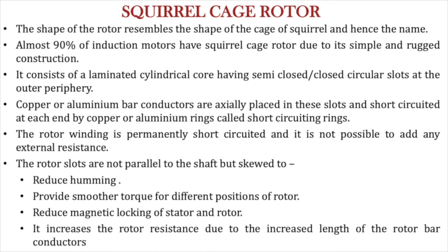The rotor slots are not parallel to the shaft but skewed to reduce the humming sound, provide smoother torque for different positions of the rotor, and reduce magnetic locking of the stator and rotor. It also increases the rotor resistance due to the increased length of the rotor bar conductors because of the slanting of the rotor slots.